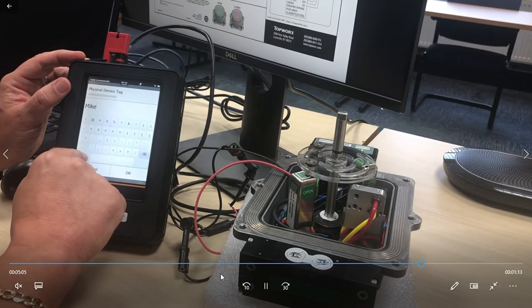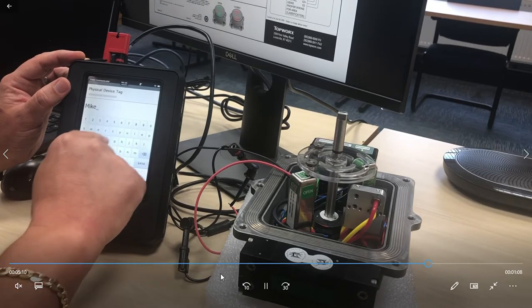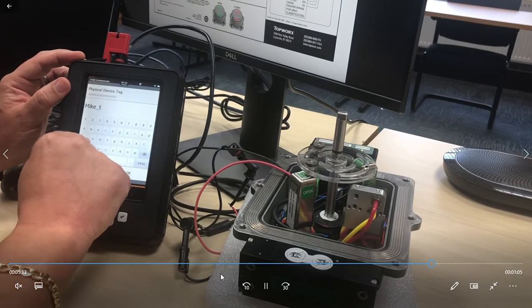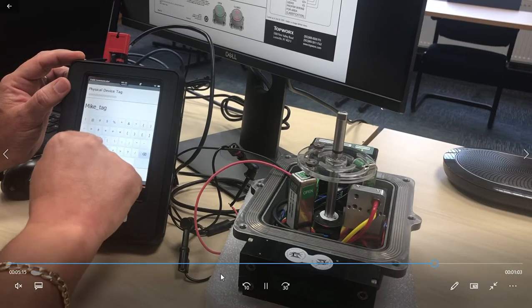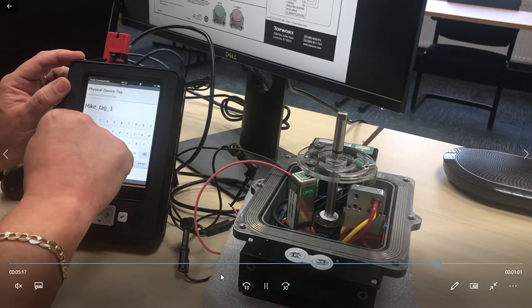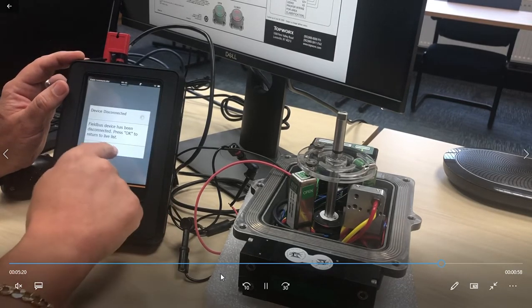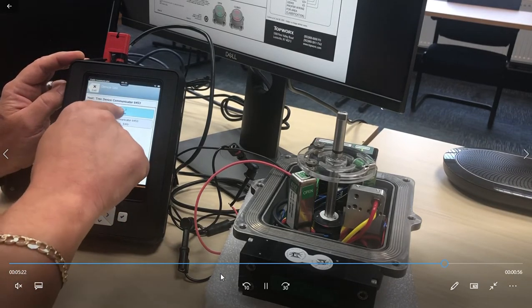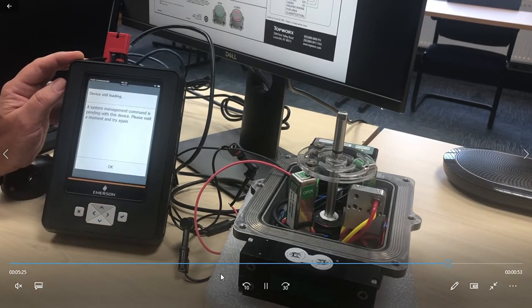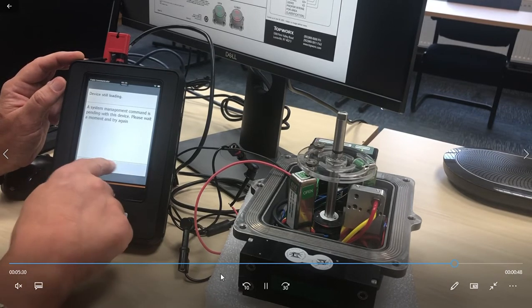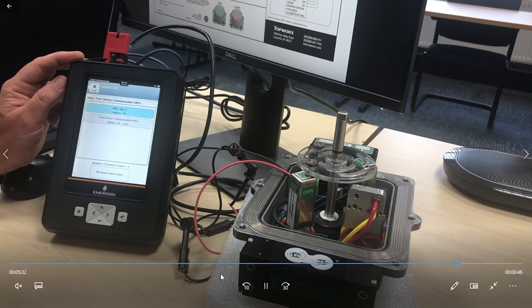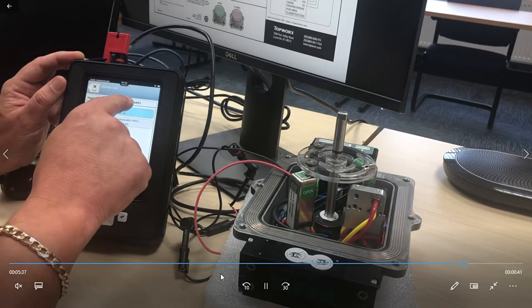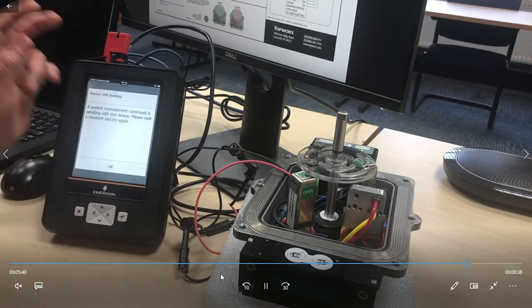But again, because it's Foundation Fieldbus, you're able to register that tag internally, electronically on the device. This is very useful because what we find, especially on a lot of sites, is that when they do maintenance and commissioning, usually the tag is on a part of the device that can be removed. In this case, sometimes we'll see it on the lid. They'll take 10 lids off, put 10 lids on the floor, and then when they put them back on the devices, they may put the wrong tag on the wrong device. But because this is electronic, it stores that information correctly.